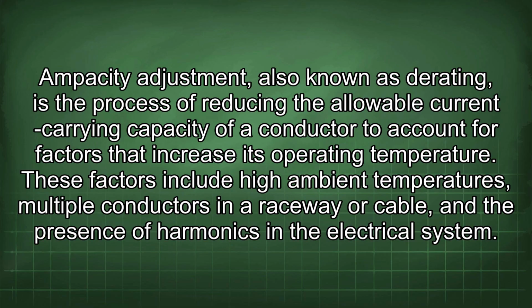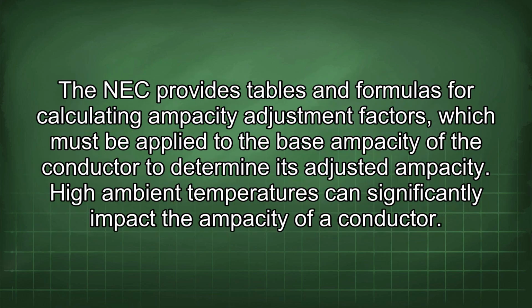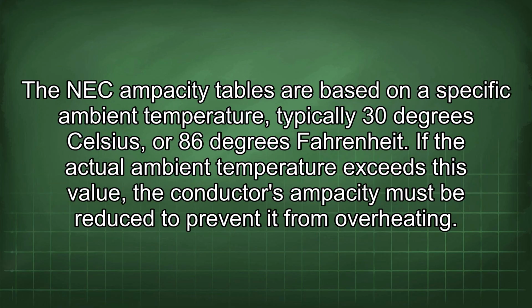These factors include high ambient temperatures, multiple conductors in a raceway or cable, and the presence of harmonics in the electrical system. The NEC provides tables and formulas for calculating ampacity adjustment factors, which must be applied to the base ampacity of the conductor to determine its adjusted ampacity. High ambient temperatures can significantly impact the ampacity of a conductor. The NEC ampacity tables are based on a specific ambient temperature, typically 30°C or 86°F. If the actual ambient temperature exceeds this value, the conductor's ampacity must be reduced to prevent it from overheating.